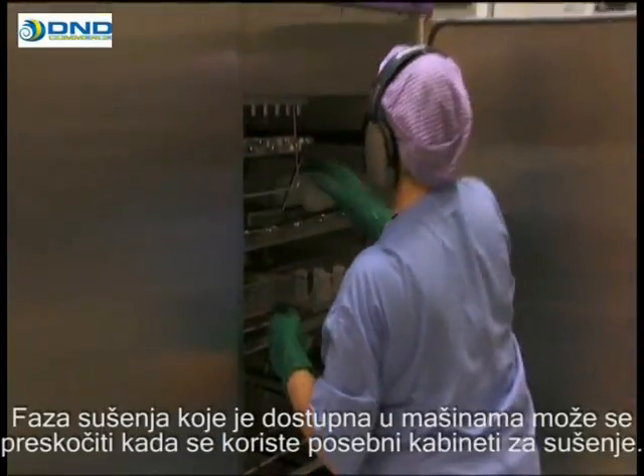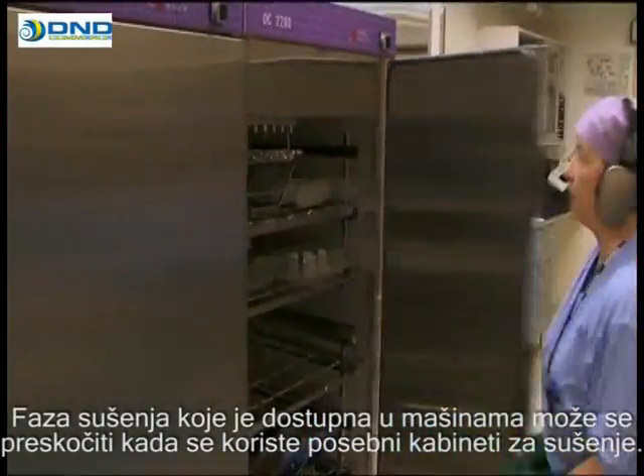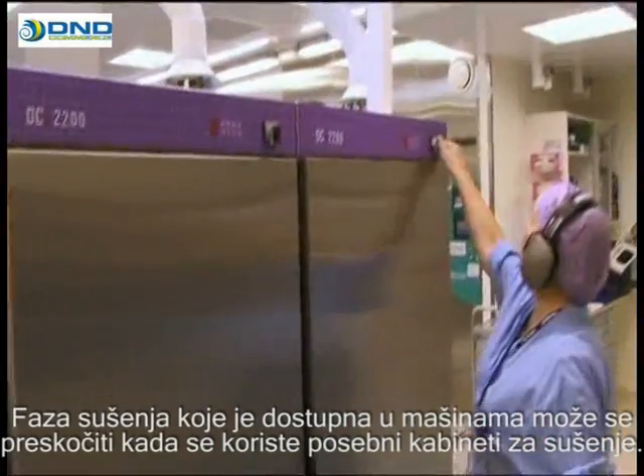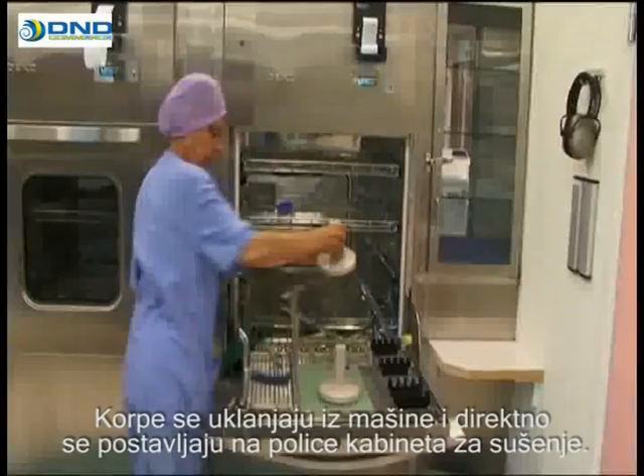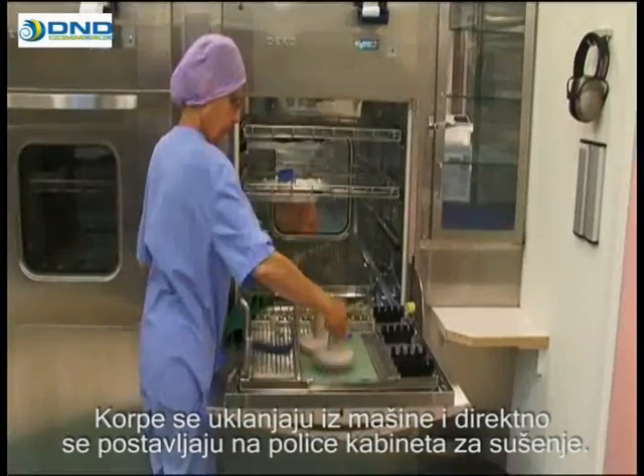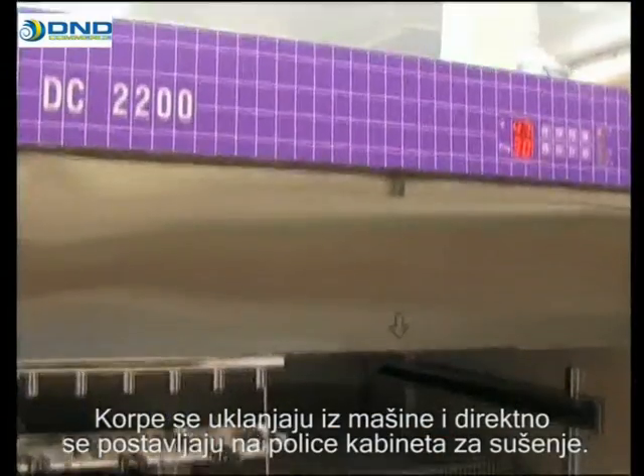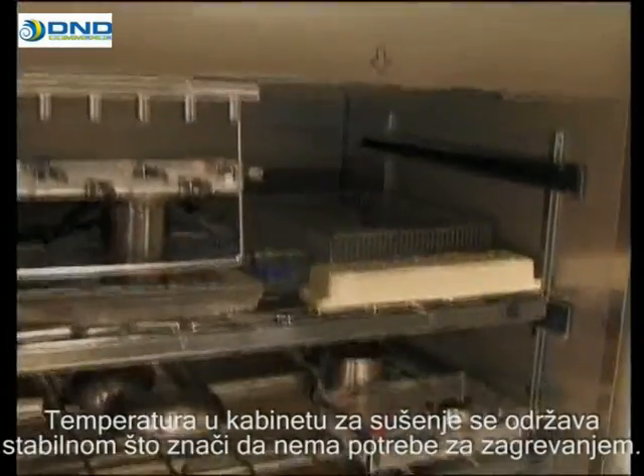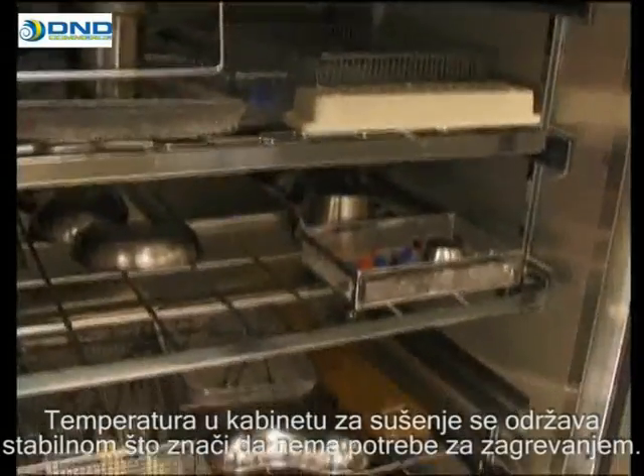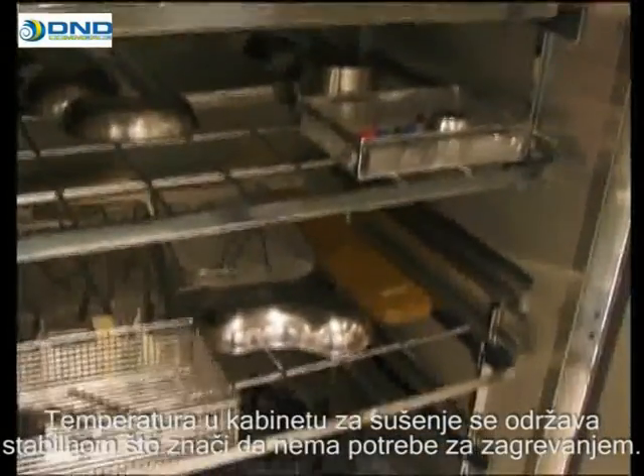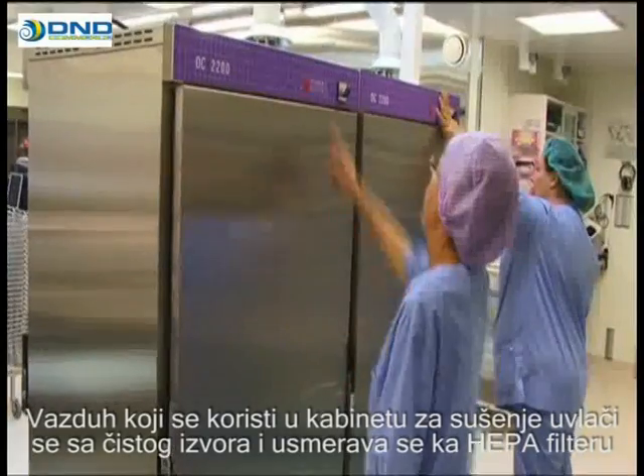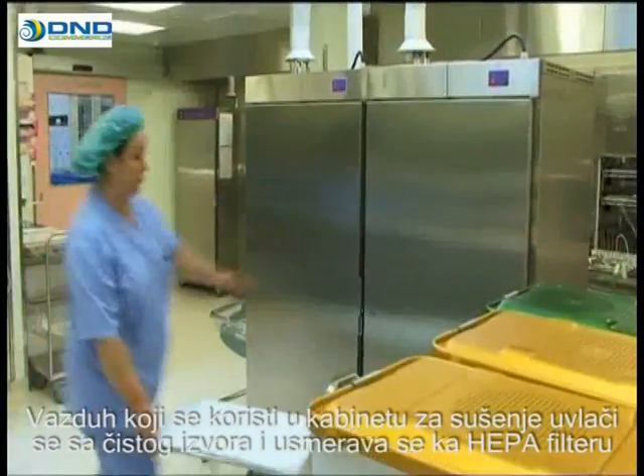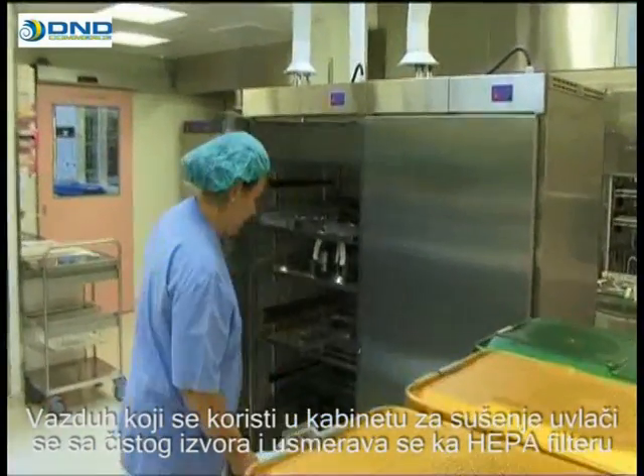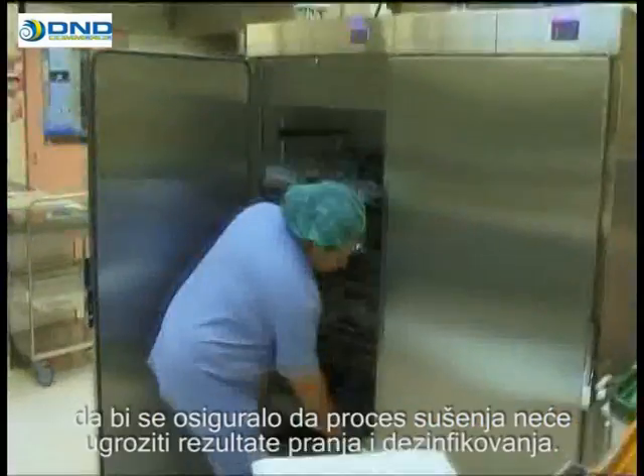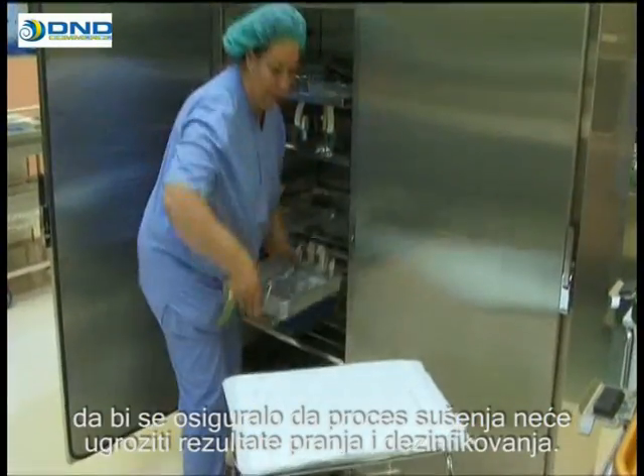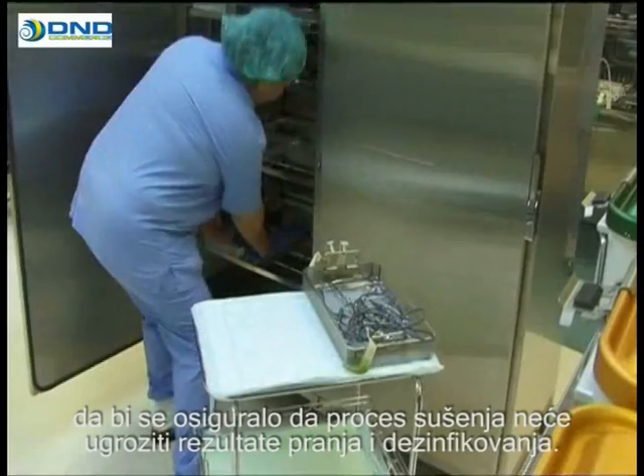The drying phase available in the washer disinfectors can be skipped when separate drying cabinets are being used. The baskets are removed from the washer and placed directly onto the shelves of the drying cabinet. The temperature in the drying cabinet is kept stable, meaning that no time is spent on heating the cabinet. The air used by the drying cabinet is drawn from a pure source and directed through a HEPA filter to ensure that the drying process does not compromise the washing and disinfection result.